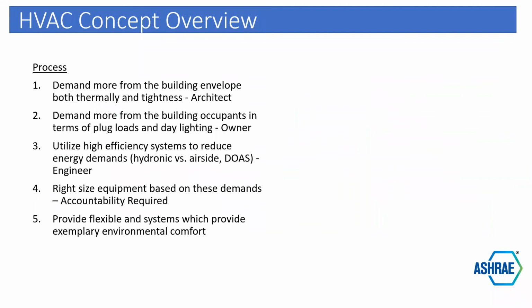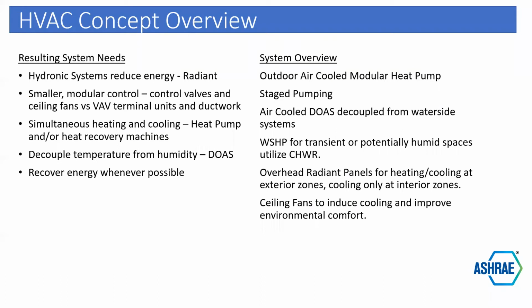So, HVAC concept overview. With the process, we demanded more from the building envelope, as I just said. We demanded more from the building occupants in terms of plug loads and daylighting. We utilized high efficiency systems to reduce energy, hydronic versus airside, with DOAS, and the right size of the equipment based on the demands, and provide flexible systems to provide great indoor environments. Resulting needs: hydronic system reduces energy, radiant system, smaller modulating control valves and ceiling fans versus VAV units and ductwork, simultaneous heating and cooling, heat pump and/or heat recovery machines. So we have a heat recovery chiller.